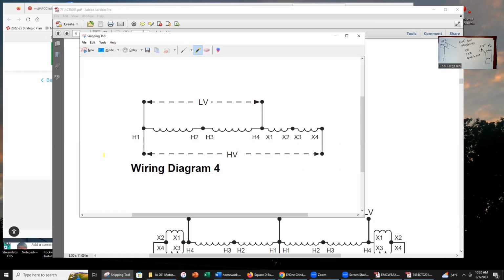This diagram shows me the different terminals inside the transformer, H1, H2, H3, and H4, as well as X1, X2, X3, and X4. Typical buck boost transformers don't have these as points like little screw terminals. They drop them out of the transformer as pigtails. So these will be individual wires dropping out of the bottom of the transformer that are clearly labeled with the H1, H2, etc. wiring diagram, and I will link you to a video showing somebody wiring this.